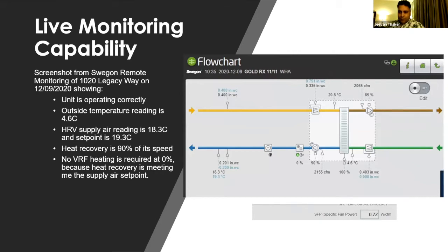This is a fun little story. If you go from right to left on this - and it's also written over there - the green arrow is always green for outside air. If you look at that number, 4.6 degrees Celsius outside, the wheel is running at 100% capacity. Here's our coil, tied to our outdoor VRF condensing unit - it's off, which is a good thing. With 4.6 degrees, with our 88.5% efficient unit, our set point was 19.3, and we're at 18.3.